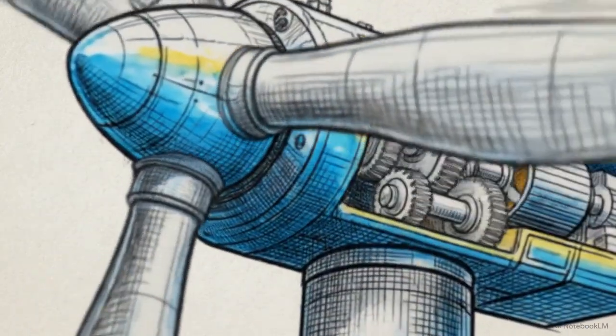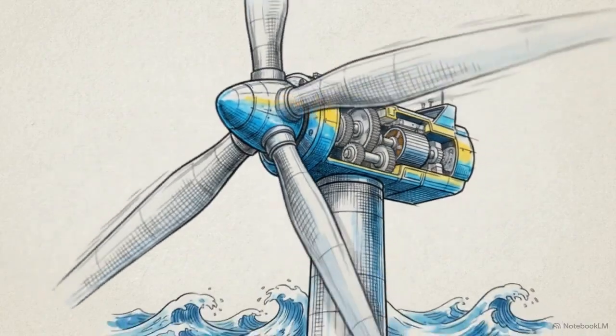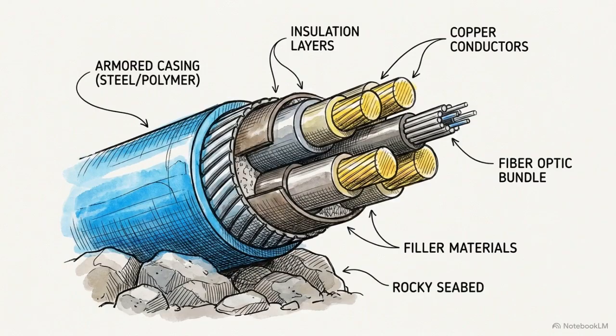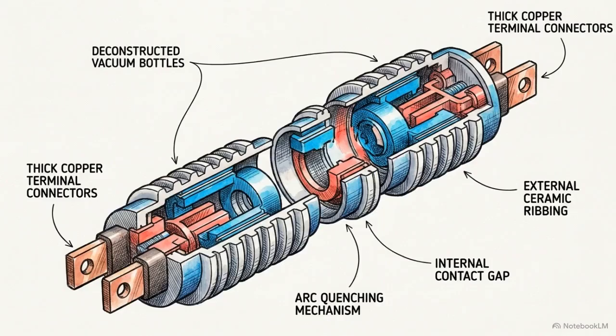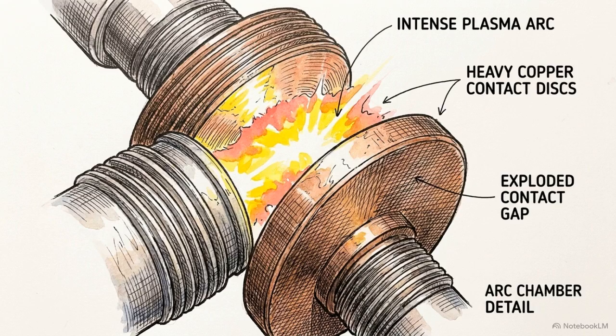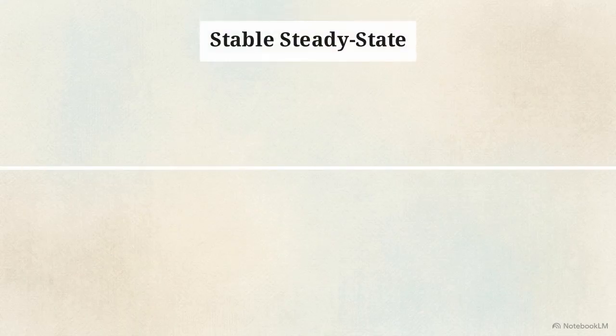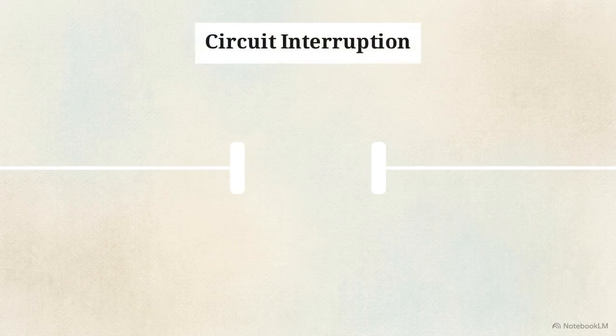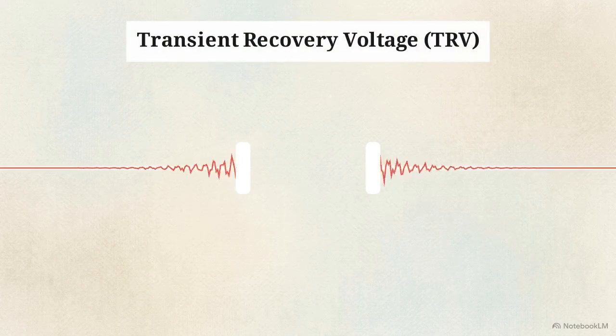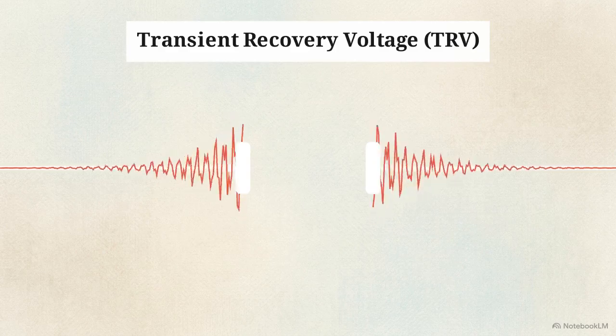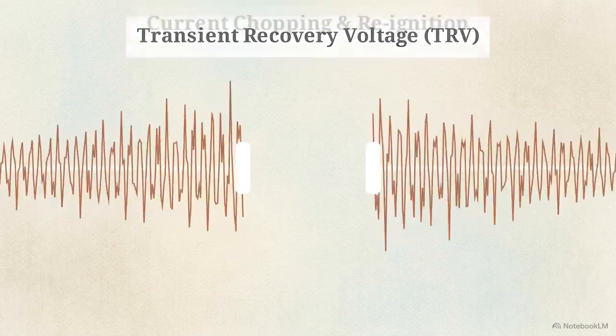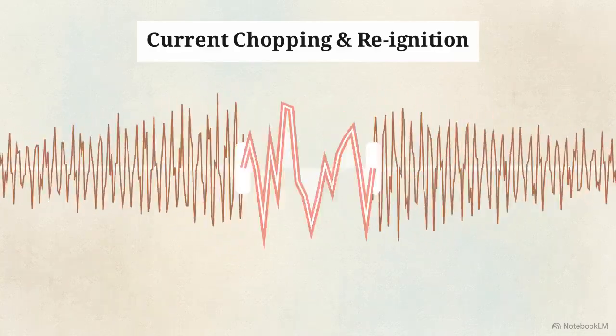These massive installations push enormous amounts of continuous power through dense, complex networks of medium-voltage collector cables. To protect these networks during electrical faults, engineers use vacuum circuit breakers, or VCBs. Their compact design allows them to reliably sever connections to stop massive surges of fault current. However, VCBs are prone to incredibly fast switching transients. When they interrupt a fault, it generates transient recovery voltage, a sudden, high-frequency voltage surge across the breaker contacts that can cause the current to chop and repeatedly reignite.